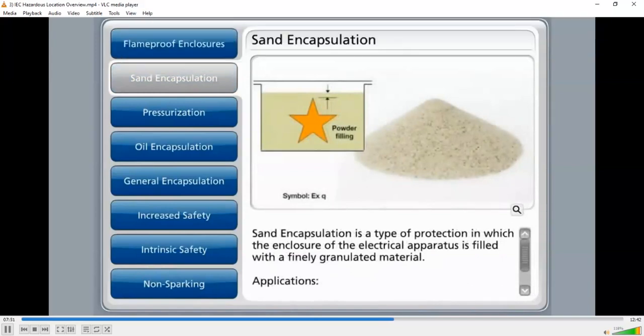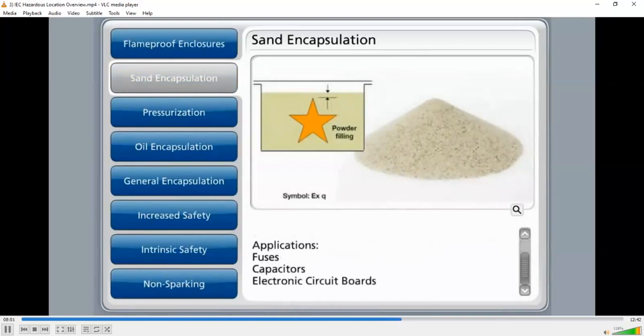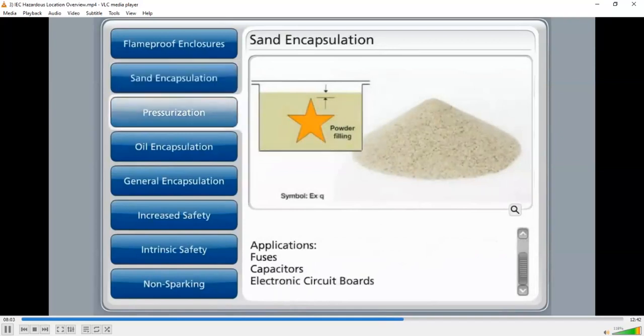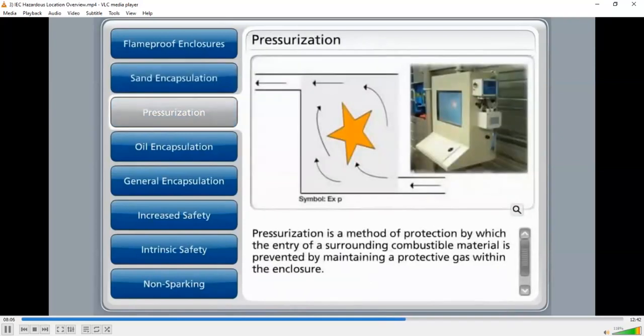Sand encapsulation is a type of protection in which the enclosure of the electrical apparatus is filled with a finely granulated material. This ensures electrical arcs occurring within the electrical apparatus will not ignite the surrounding atmosphere. Pressurization is a method of protection by which the entry of a surrounding combustible material is prevented by maintaining a protective gas within the enclosure. This is generally accomplished by creating a higher pressure within the enclosure than the surrounding atmosphere. This protective method would be used for any power-operated equipment.